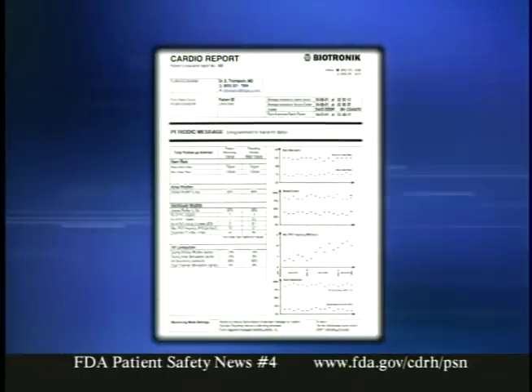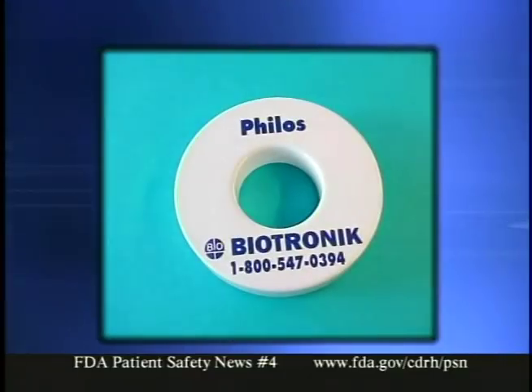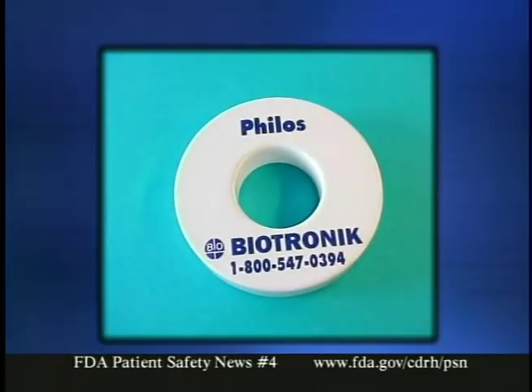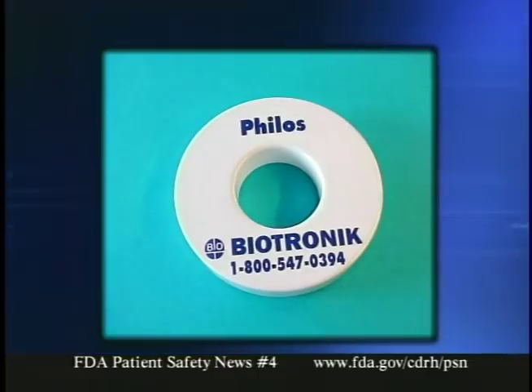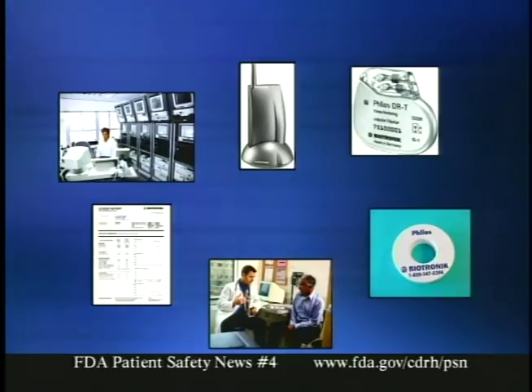The information is then faxed to the physician's office at pre-set intervals ranging from once a day to once a month. The company also accumulates the data and can provide the physician with trend information on the patient's heart over a period of time. The physician can also program the device so that it sends data whenever the patient places a magnet over the pacemaker, allowing the patient to notify the physician when unusual symptoms are occurring. This home monitoring system is not a substitute for regularly scheduled office visits — it's designed to provide supplementary data between those visits, and it can't be used in areas not covered by cell phone service.